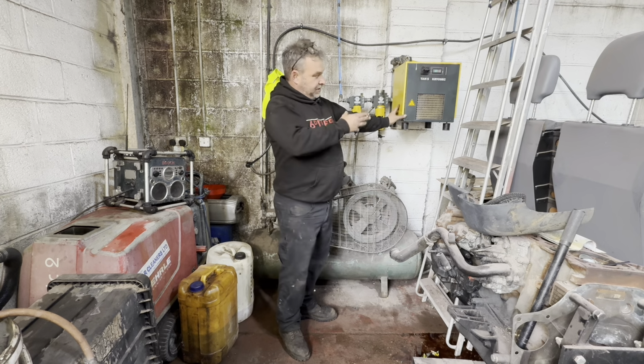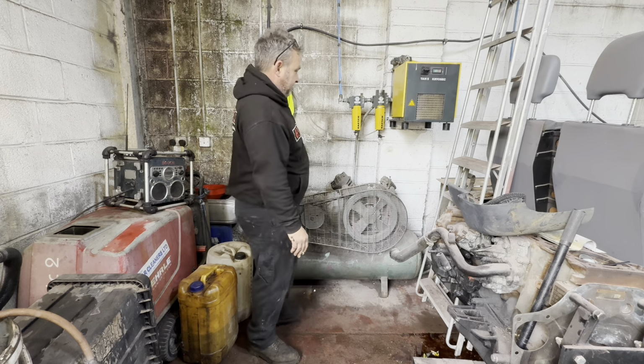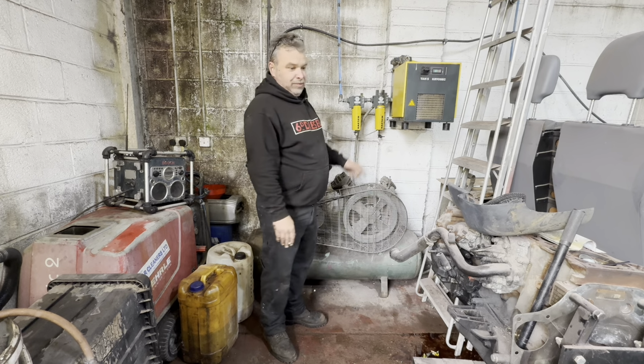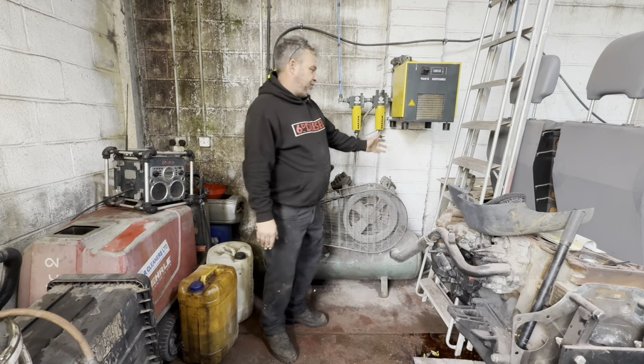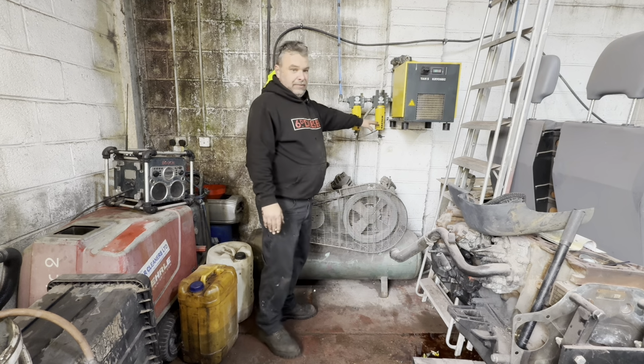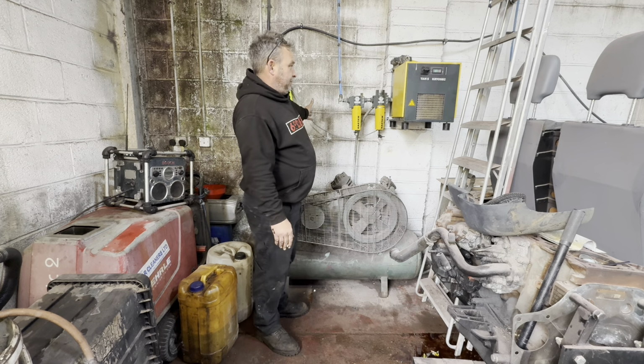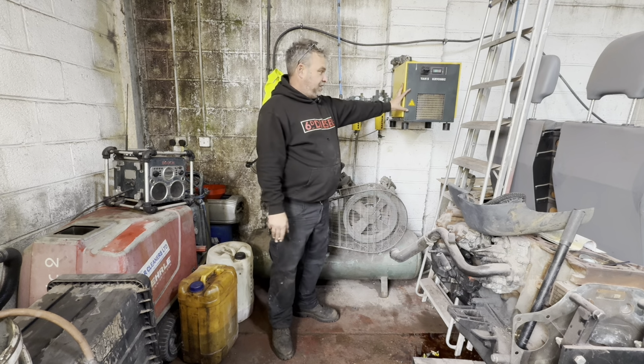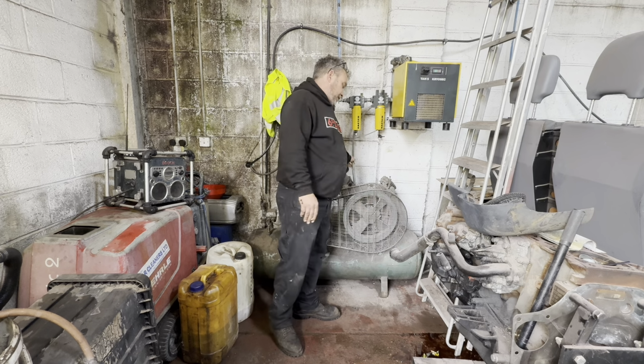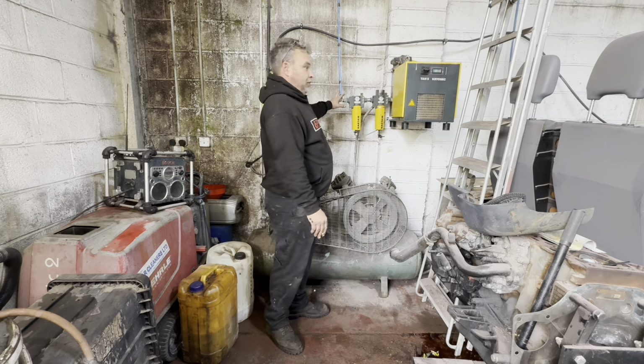So this is an air dryer. This is a separate air dryer, which was on a stand here for ages because it was originally designed to sit on these little feet. But that's a crap idea because it falls over all the time. There were 3 of these, I've slimmed it back down to these massive automatic water separators hanging off the side of it, which catch moisture. So this is like a little air conditioning unit. Basically what it's doing is cooling the air coming out of this compressor tank here, and then any moisture coming out is caught before it gets into the air main.